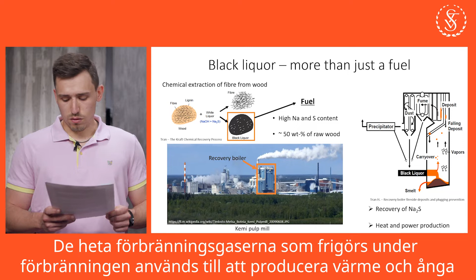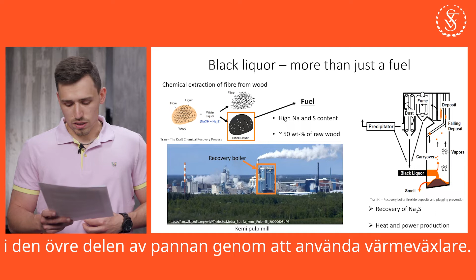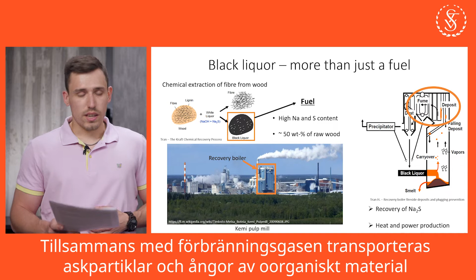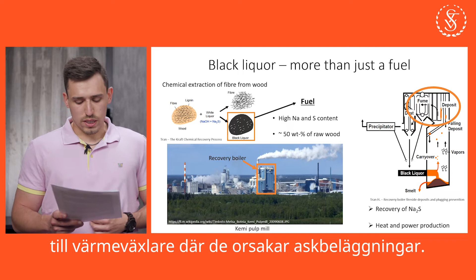Hot flue gases released during combustion are used to produce heat and power in the upper region of the boiler using heat exchangers. Together with the combustion gases, ash particles and vapors of inorganic compounds are transported to the heat exchangers, where they cause deposit formation. Here you can see clean heat exchanger tubes.